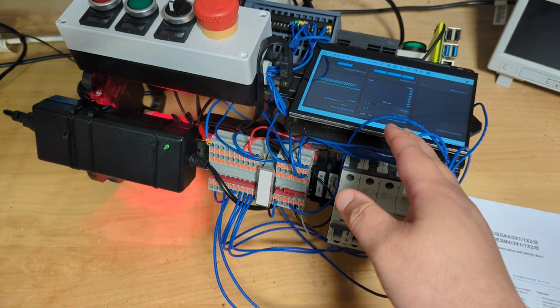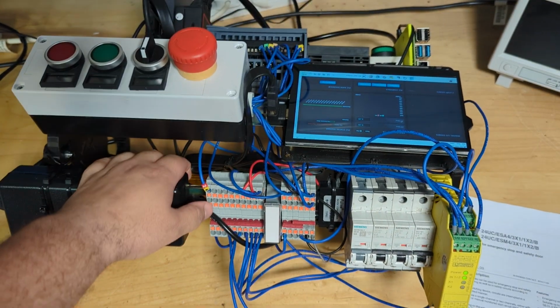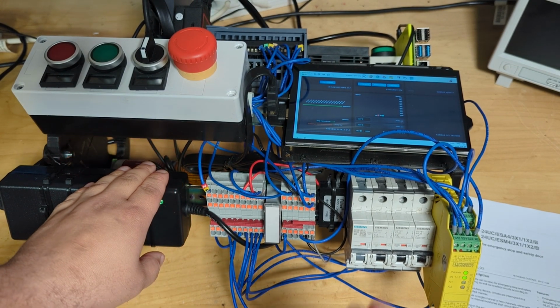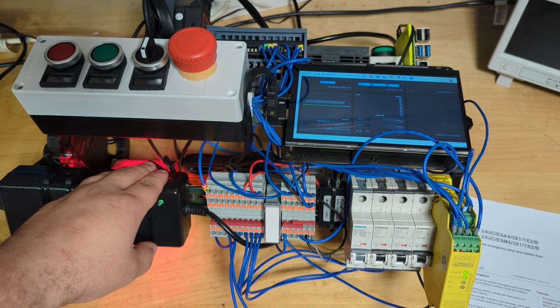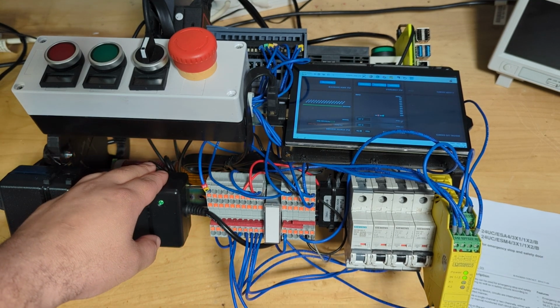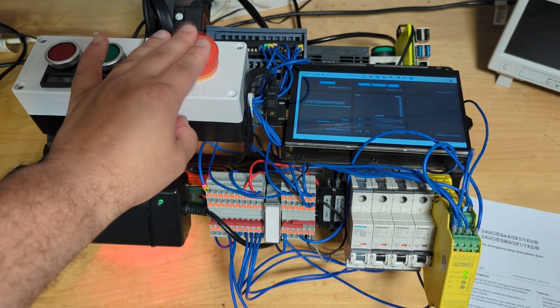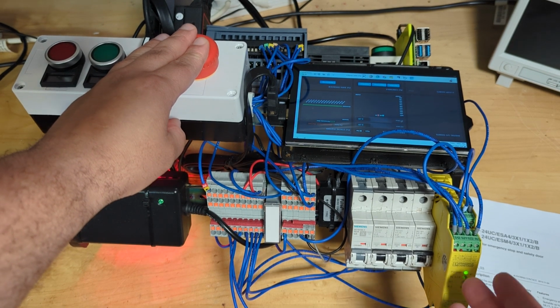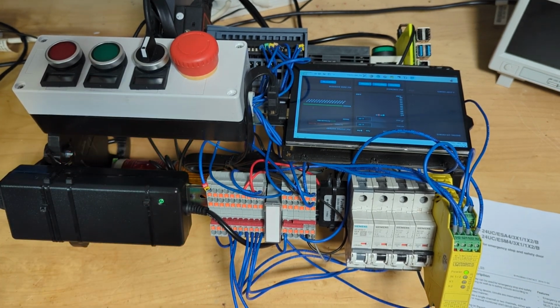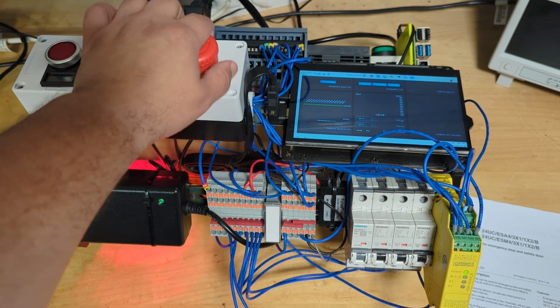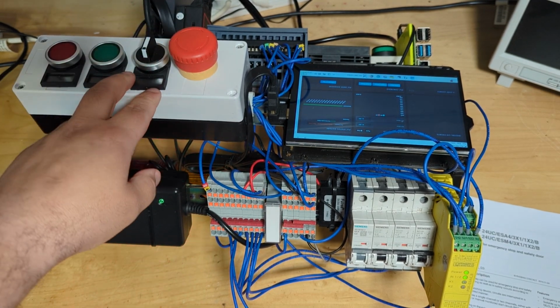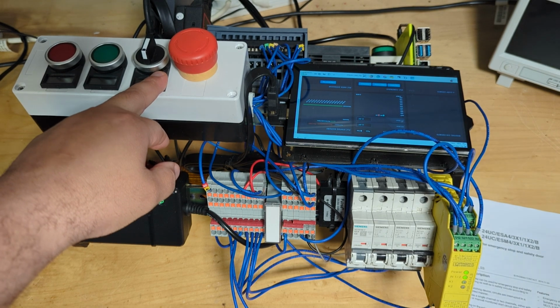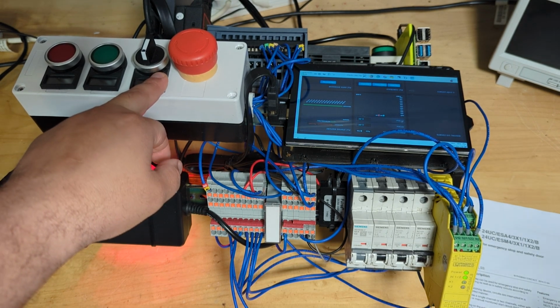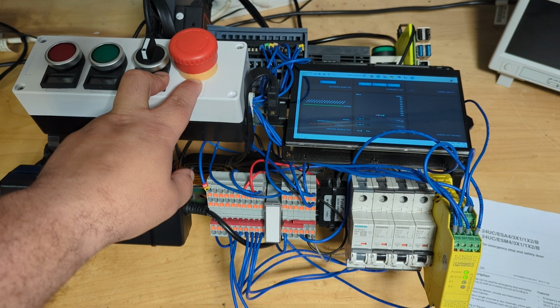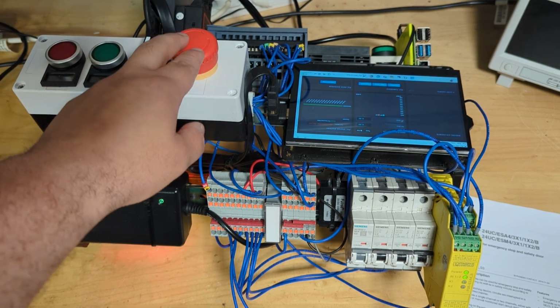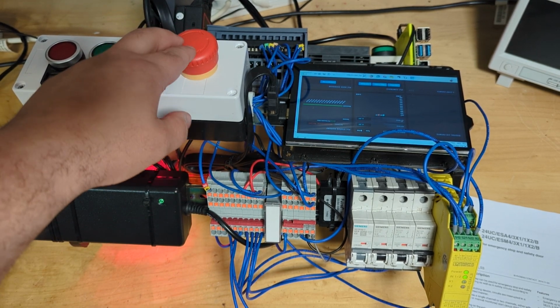I guess probably the best place to start is, talking to a guy that I work with, he's somewhat of a new graduate at work. I guess the most common misconception of e-stops is that when you're hitting that, you're disconnecting power, but you're not. You can see this LED is still on at the back. You don't really want to kill power, especially not to your control circuits. You're killing power to maybe some circuits, so an output to a valve or to a motor, but generally this signal here, I want it to go into my system.